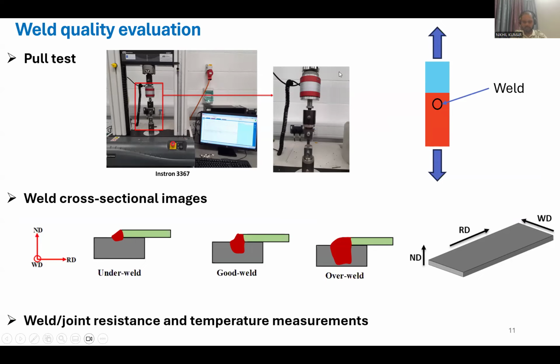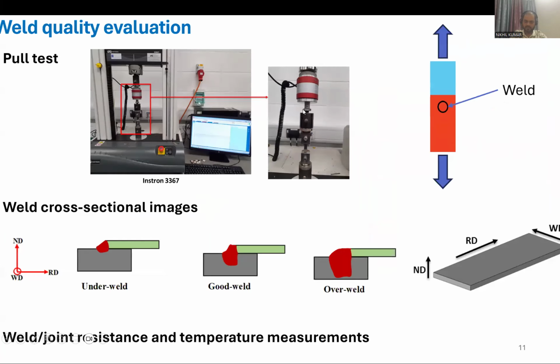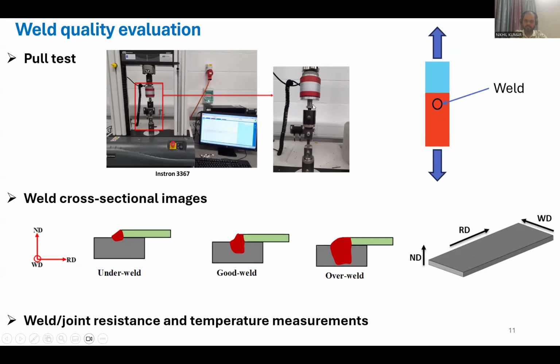How is the weld strength captured? It's captured in the load cell. You can use a load cell to capture the resistance. The specimen is gripped on the bottom, which is stationary, while the top is moving, capturing the strength, or maximum load, using the load cell. This way you can determine whether it's a good or bad weld, depending on whether it fails from the tab or has an interfacial failure.